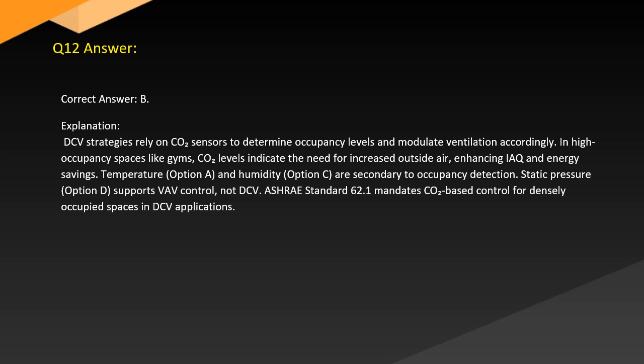Answer. Correct answer: B. Explanation. DCV strategies rely on CO2 sensors to determine occupancy levels and modulate ventilation accordingly. In high occupancy spaces like gyms, CO2 levels indicate the need for increased outside air, enhancing IAQ and energy savings. Temperature, option A, and humidity, option C, are secondary to occupancy detection. Static pressure, option D, supports VAV control. ASHRAE Standard 62.1 mandates CO2-based control for densely occupied spaces in DCV applications.